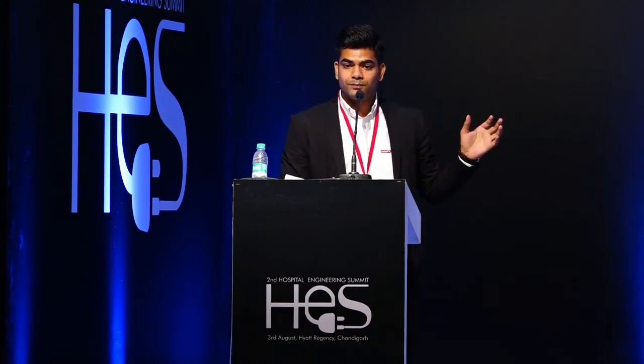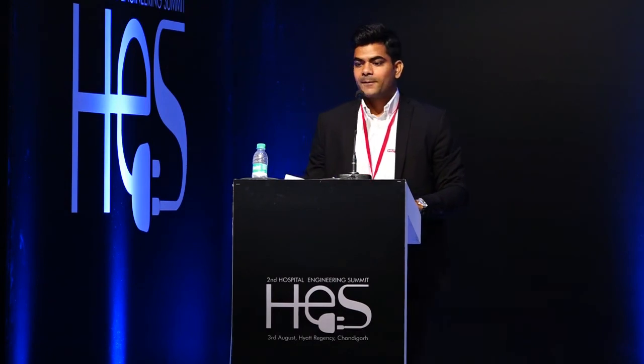This excerpt is from the FM Global guideline. FM Global is regarded as one of the most stringent sprinkler guidelines in the world. Then comes NFPA. Even in the stringent one, I did the calculation - 7 sprinklers. The moment you open the 8th sprinkler, you're overtaxing the entire design. This is where the fire stop system comes in - you should contain the fire within that compartment so you don't open more and more sprinkler heads, keeping the fire contained and easier to suppress, which is the intention of the sprinkler as well.